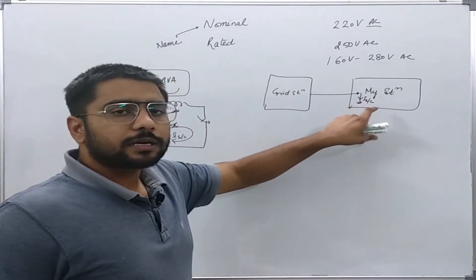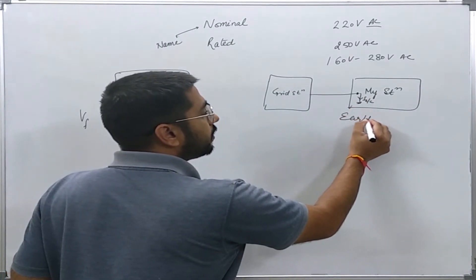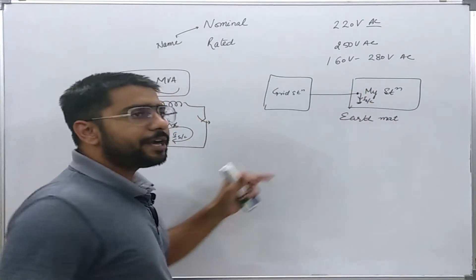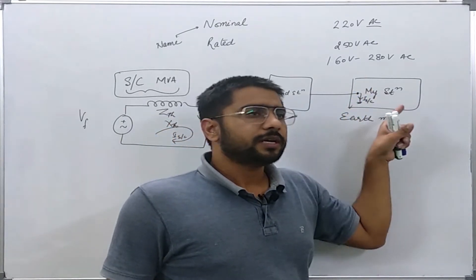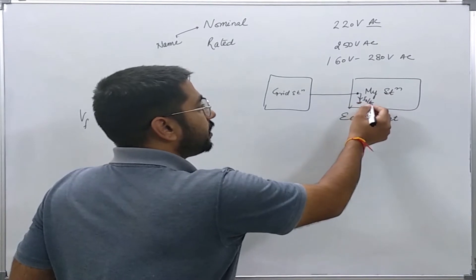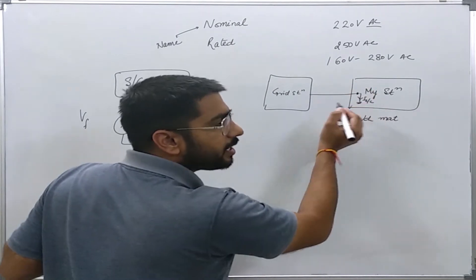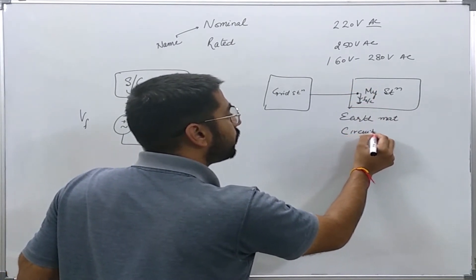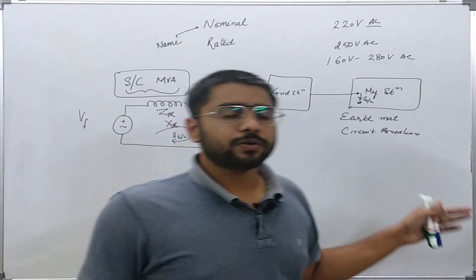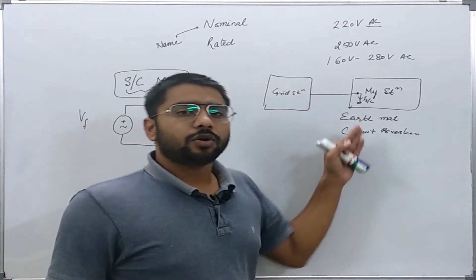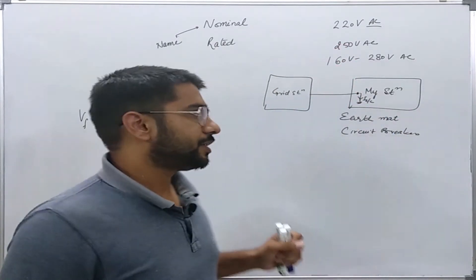This current value is very crucial. For designing an earth mat, whenever a line-to-ground fault occurs with current flowing through the ground, I need that current to redesign the earth mat. Similarly, this current will have to be interrupted by circuit breakers, and various equipment in between will also have to carry that current. So this fault current determines many rated values for equipment being used in the substation.